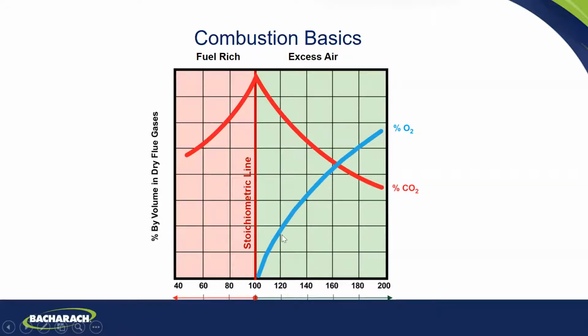So I really like to read oxygen. I'm not so concerned about the reading of excess air or CO2 because I know my oxygen is what the analyzer is using to calculate those. The reason we don't use CO2 and we use oxygen is because CO2 is on both sides, as you've noticed on this combustion chart. I could be reading 8% CO2, and I actually don't know which side of combustion I'm on.